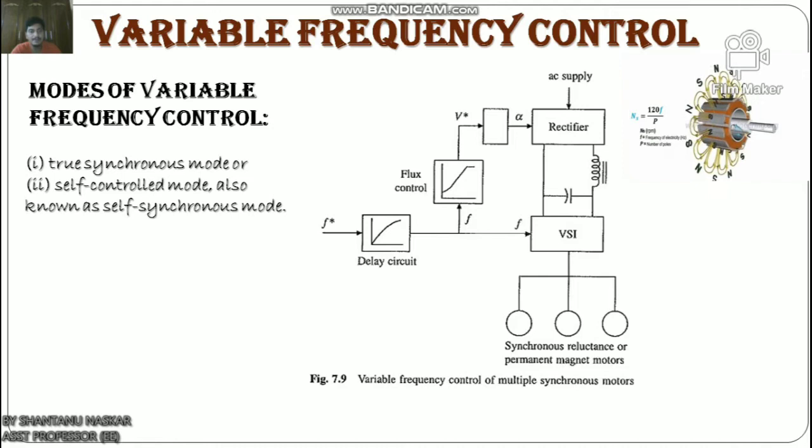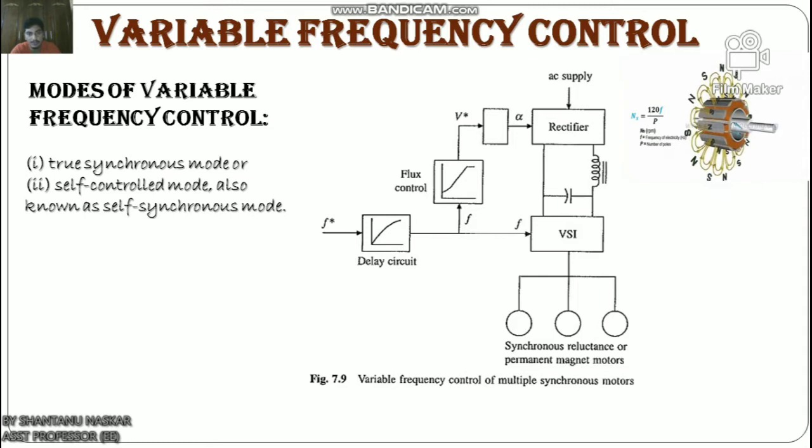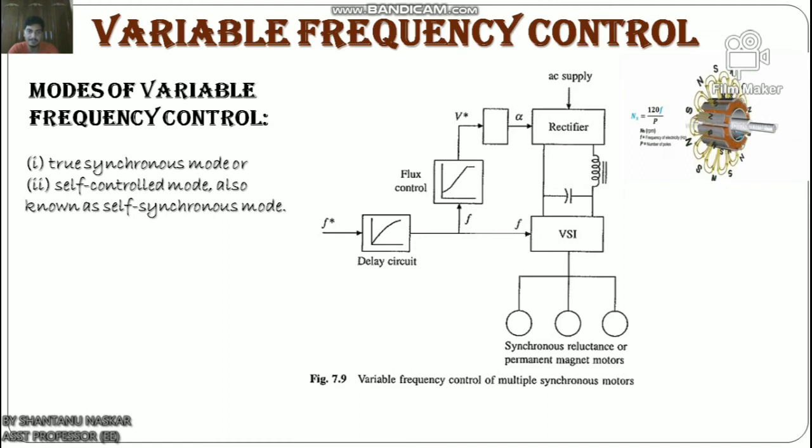Variable frequency control of multiple synchronous motors can not only allow speed control but can also be used for smooth starting and regenerative braking, as long as it is ensured that the changes in frequency are slow enough for the rotor to track changes in synchronous speed. A motor with damper winding is used to pull into synchronism.